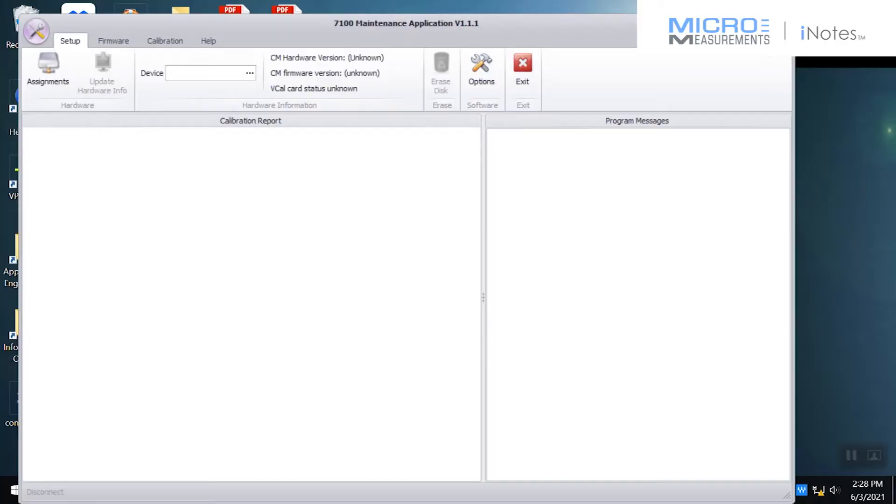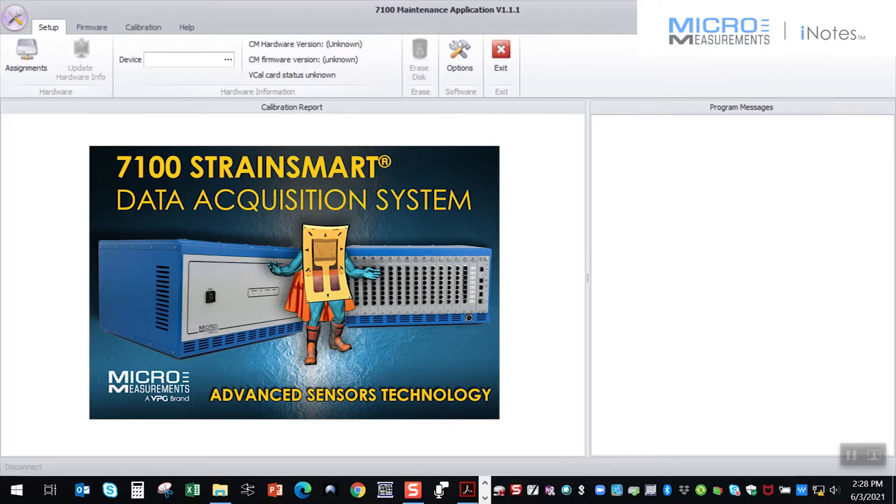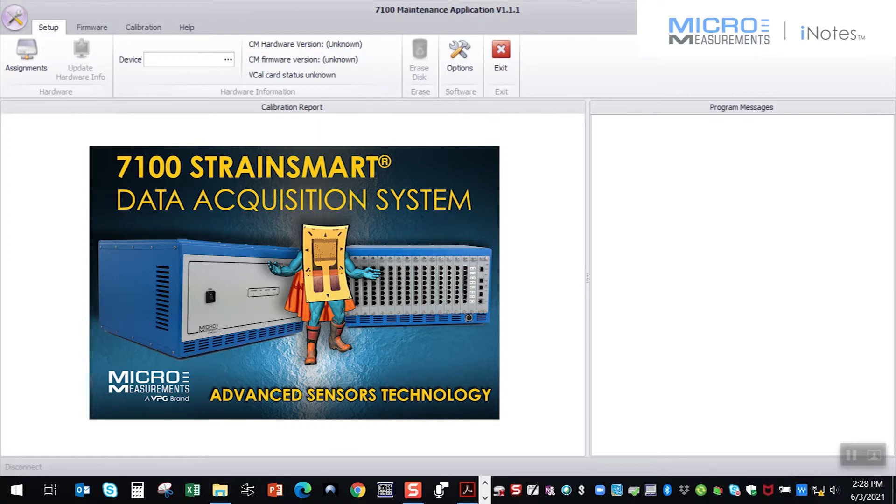And the 7100 scanner, as Paul mentioned, comes with the VCAL card. So that means that you as the user can calibrate that scanner as often as you want to. Typically from the manufacturer, we'd recommend that you do it once a year. But if you want to do it once a week, once a day, it's totally your option as far as how often you calibrate it. And this has probably been one of the biggest advancements we've had in our data acquisition systems is the ability for them to be field calibratable by the user. Back in the old days, you used to have to pack everything up and ship it to us and we'd calibrate each individual card at the time. And what that led to was quite a bit of downtime. And now virtually there is no downtime with the 7100 scanner.